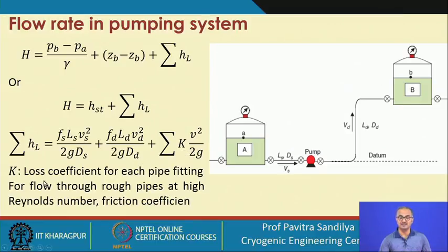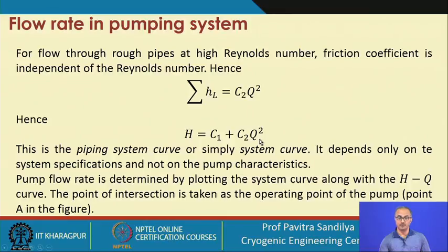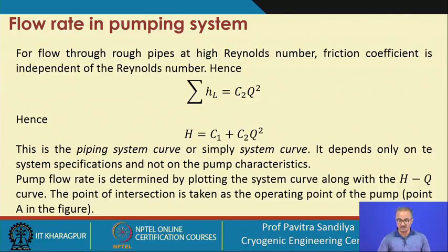With this assumption we simplify the equations to find the total head. The total energy loss due to friction includes the friction factor contribution on the suction side, on the delivery side, and losses in the various fittings and valves, accounted for by a loss coefficient K. For flow through rough pipes at high Reynolds numbers, the friction coefficient is independent of Reynolds number, so the head loss becomes a function of Q squared. This gives the relationship: H = C1 + C2 Q², called the piping system curve or system curve, which depends only on the system specifications and not on the pump characteristics.